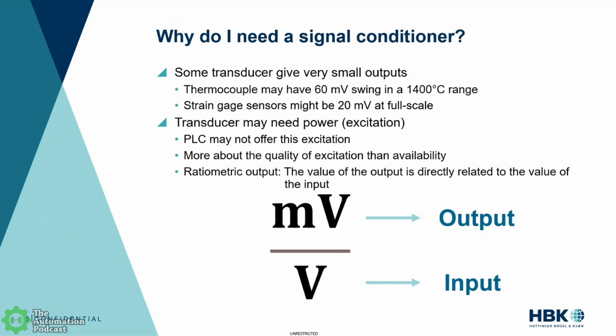That being said, you have to be very confident that you are feeding this exactly 10 volts. Because if you're feeding it 10.1 volts or 10.2 volts, if it's not a highly regulated voltage source, your output could be greater or smaller than what you're anticipating. Now you have greater uncertainties, and you're not exactly sure of what you're measuring here. And to manage that in the PLC would be a nightmare, because you'd have to bring in the voltage and actually run this formula inside the PLC. So if you have a voltage output for your strain gauge that is going to maintain 10 volts precisely, or whatever the voltage is, then you don't even have to worry about that. You know that the power supply is taken care of, and it's just going to be reliable.